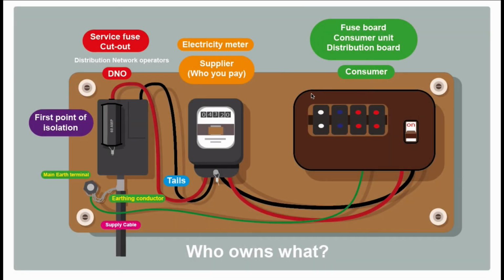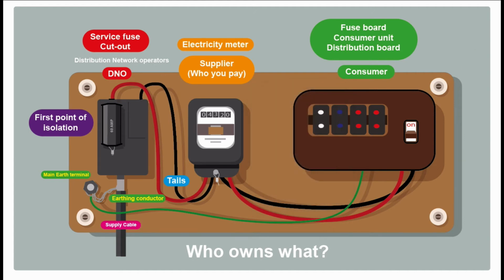It's their responsibility. Sometimes the client wants to have the consumer unit, the fuse board, in a different location. That's okay, we can do that relatively simply. We'd put a switch fuse here, run armoured cable from there to the new location, and you can mount your new consumer unit wherever you want it, really, within reason. But what we can't do, we can't move the meter and we can't move the service head. If you wanted to move the meter, you'd have to get in touch with the meter people, the supplier, and they'd have to do that.